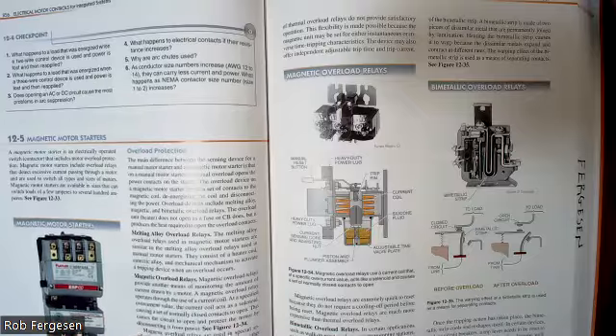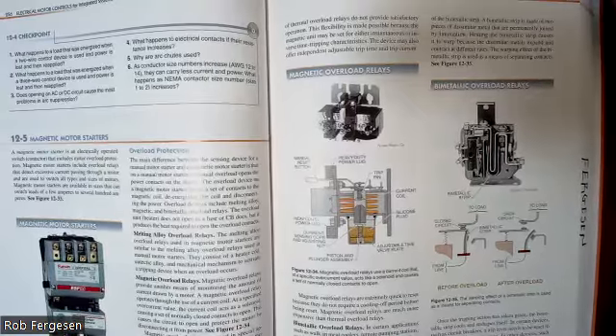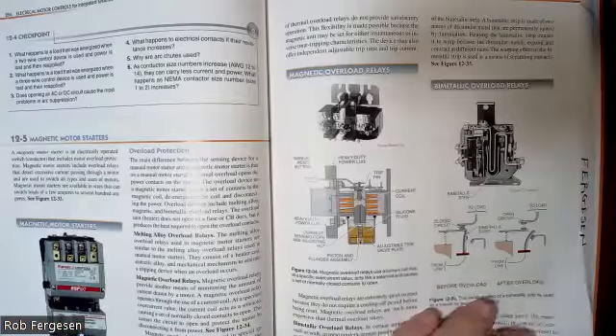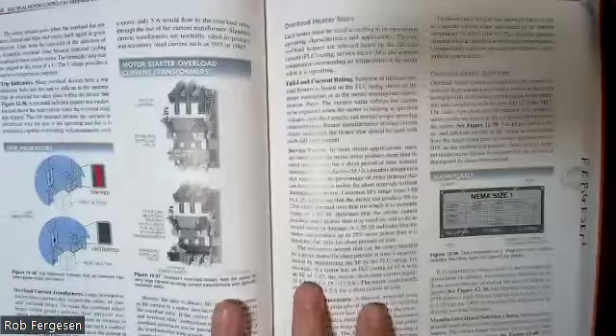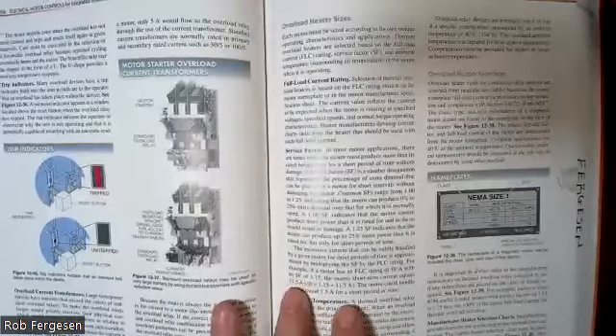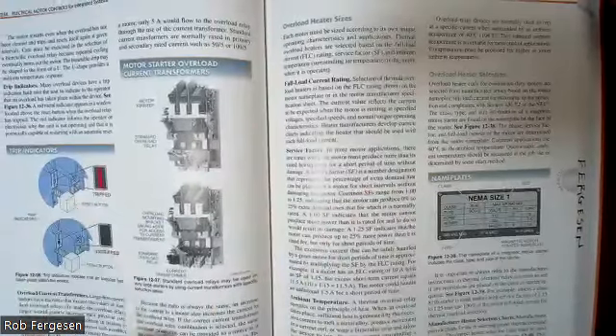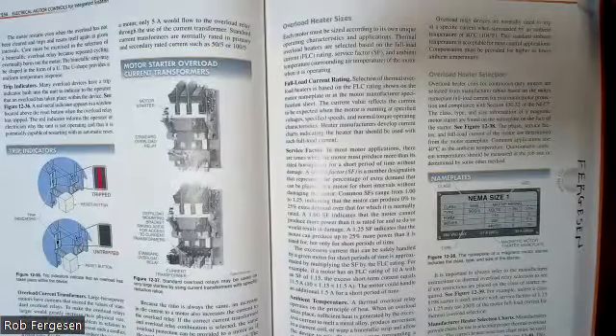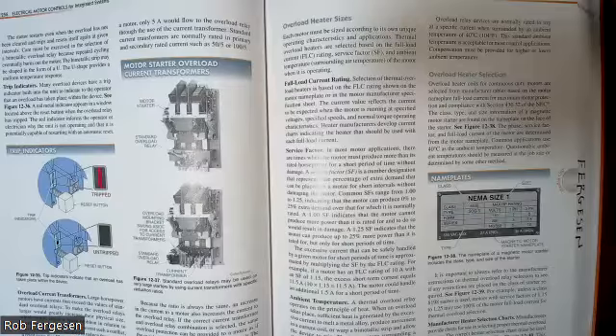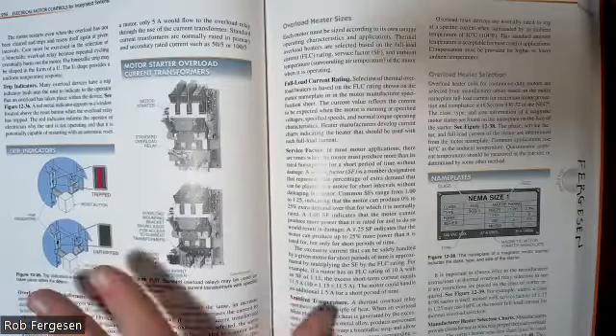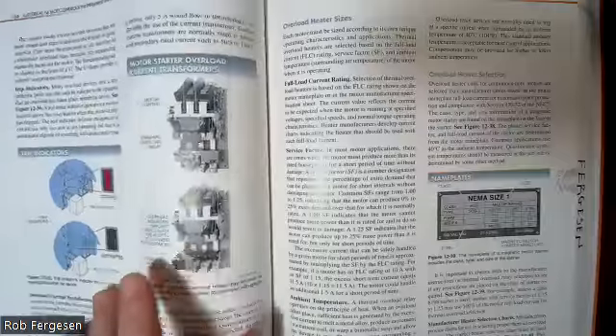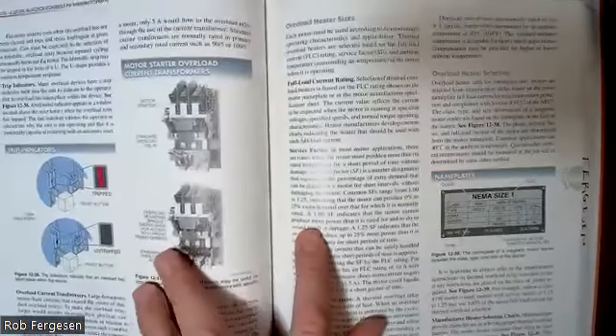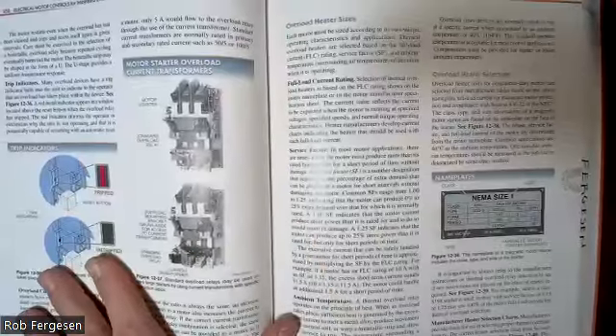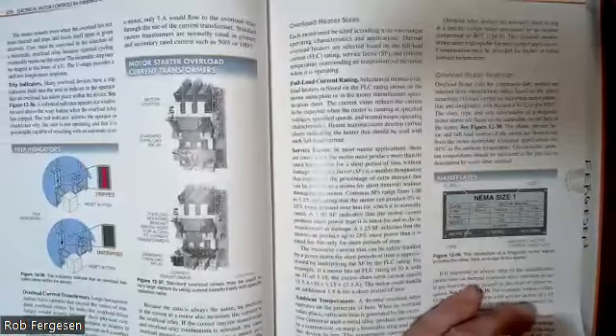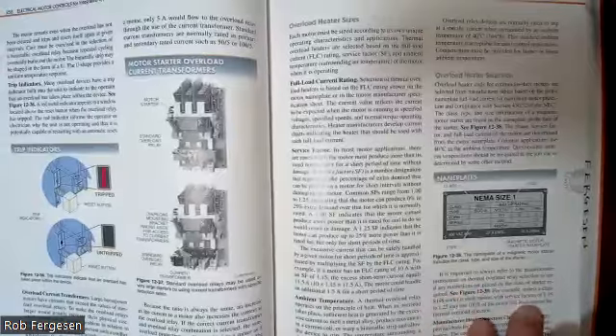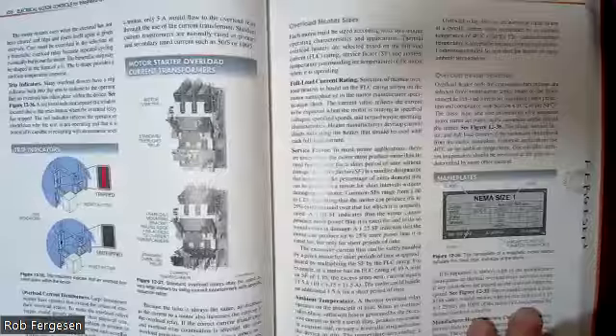And so there's a couple different styles of motor protection. This takes you through some of those. You can read about that. They have a variety of trip indicators. Sometimes you get a big red button that pops up. Sometimes you get a little light. Sometimes you get a little red flash indicator, depending on the method. So each motor starter is going to have a different method of indicating that it's tripped. And some of them aren't going to be very obvious. Talks about setting up the heater sizes, the overload heaters. Heaters is a slang term for that protection.